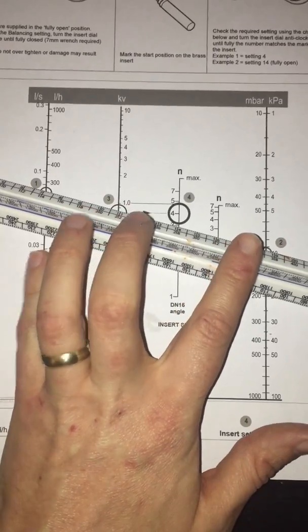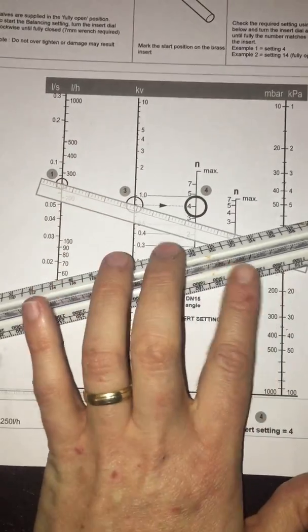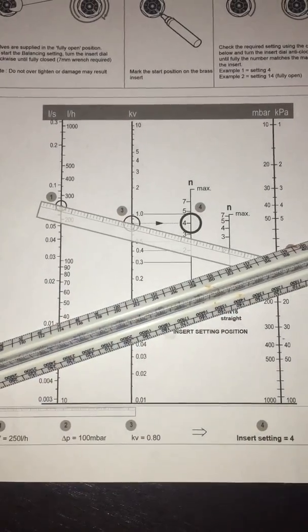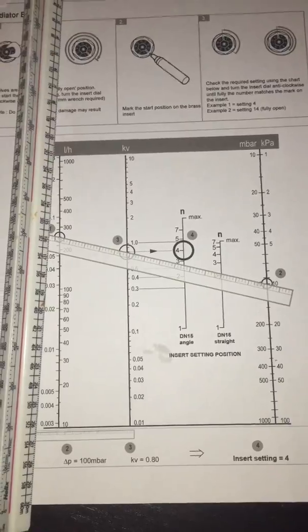Now, larger radiators, we want less resistance, so we will want a higher KV value. And smaller radiators, we will want higher resistance and therefore a lower KV value. Okay, so thank you for listening and any questions, just ask.